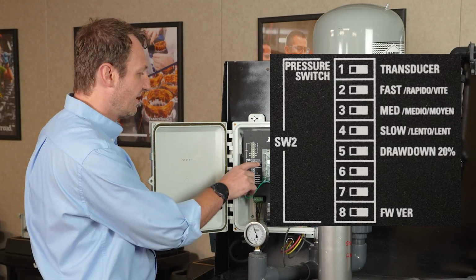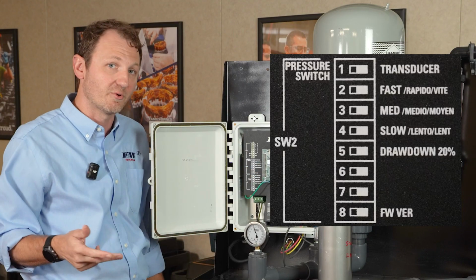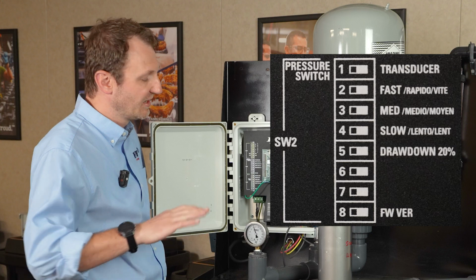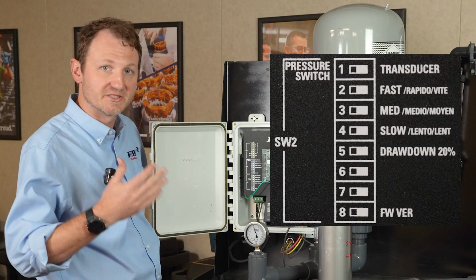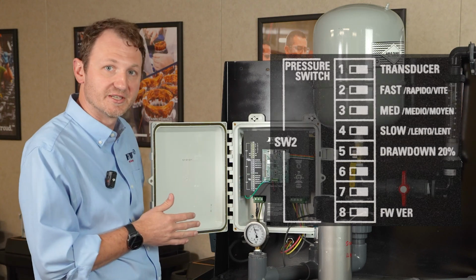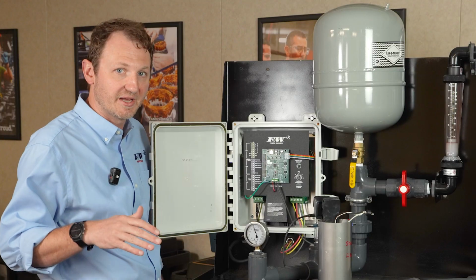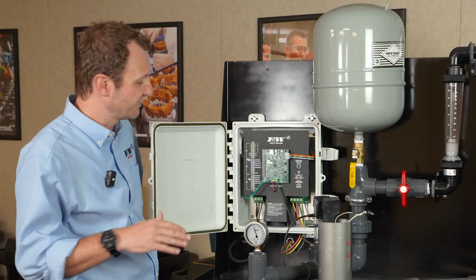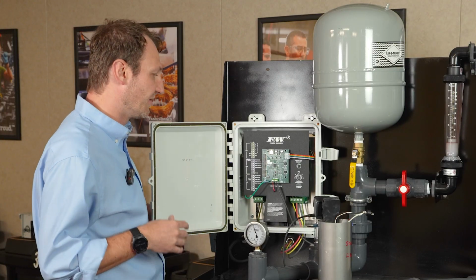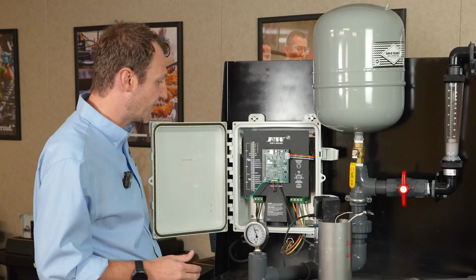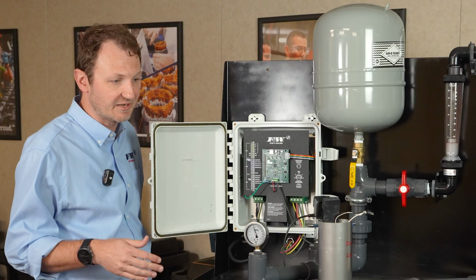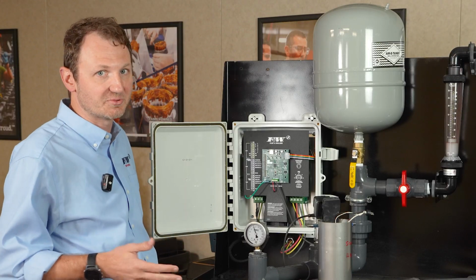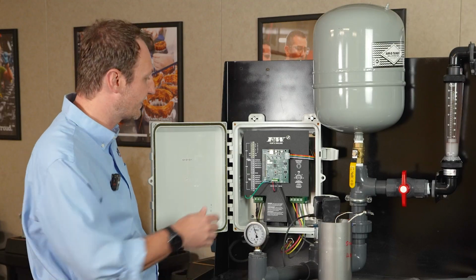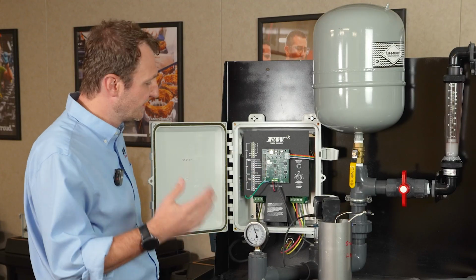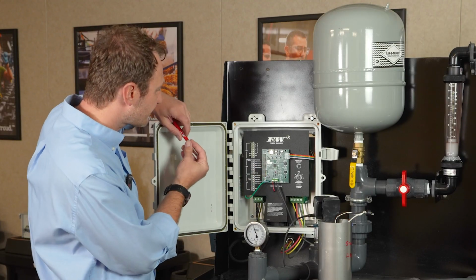That's on. The next 3 options, 2, 3, 4, are fast, medium, slow. That is just reaction time between the drive and the transducer. I typically recommend you just leave that off. That's not something that you normally would have to adjust, but if you do notice excessive pressure fluctuations at startup or while running, you can go ahead and increase the sensitivity there.